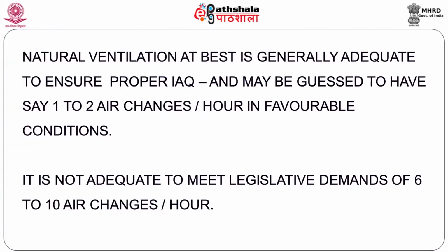May not be useful for control of environment to make it habitable for a person, not in the tropics, but equipment definitely can be very well served by natural ventilation. This is a repeat of what I just mentioned, that natural ventilation can give you perhaps 1 or 2 air changes per hour, which is absolutely enough to maintain good oxygen levels and perhaps indoor air quality, but perhaps not enough for thermal comfort, for which you might have to look at higher levels.